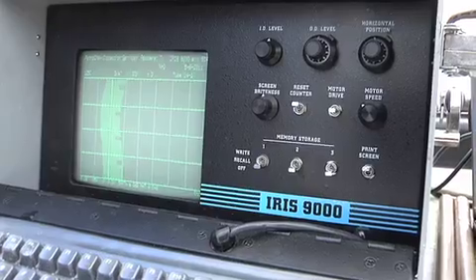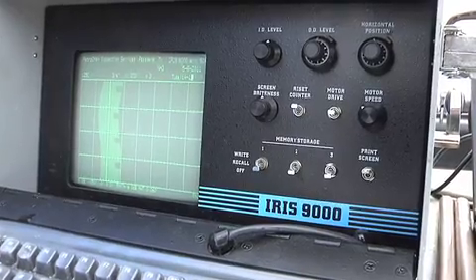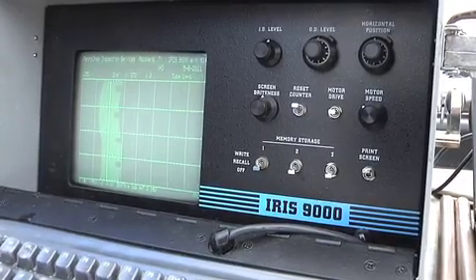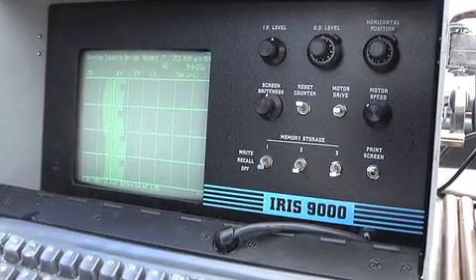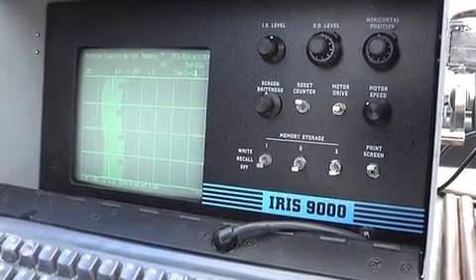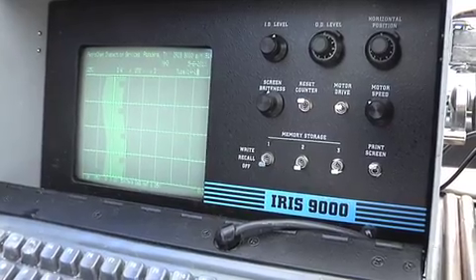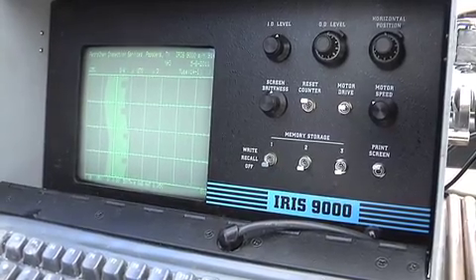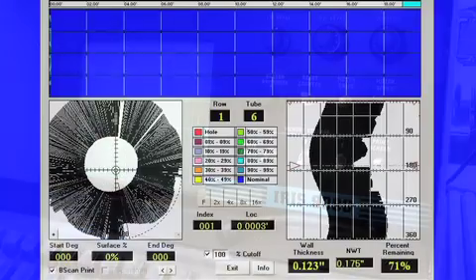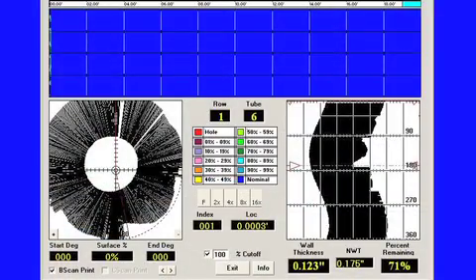We have four flat-bottom pits. IRIS only reads the lowest minimum wall. So the lowest minimum wall is reading at about 50 mils. I can give you an actual wall remaining.